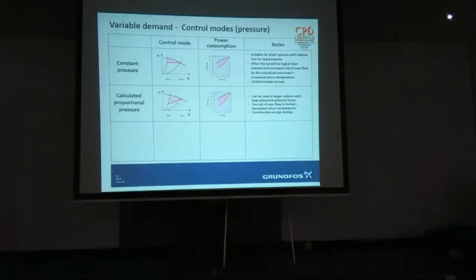method. Calculated proportional pressure is where it's built into the pump, where you might have sensors across the pump, and then the algorithms in the pump say, well, I'm slowing down. If I work on a slope of 50% or 30% or whatever, it works down a line like that. One of our pumps works on 50% standard, and other pumps we can actually alter the slope. That's a greater method of saving energy. And it's also great because you don't have to run miles of pipe cables throughout the building to put your sensors at the furthest point. So it's built into the pump. Or it can be built into a control.